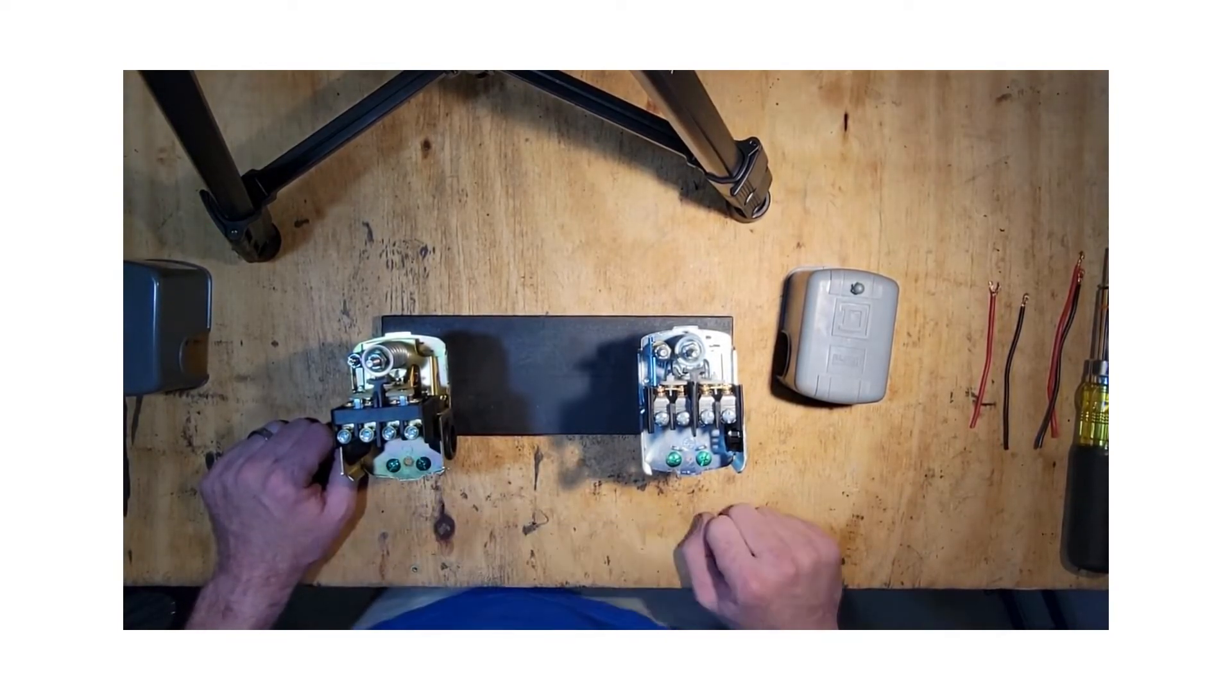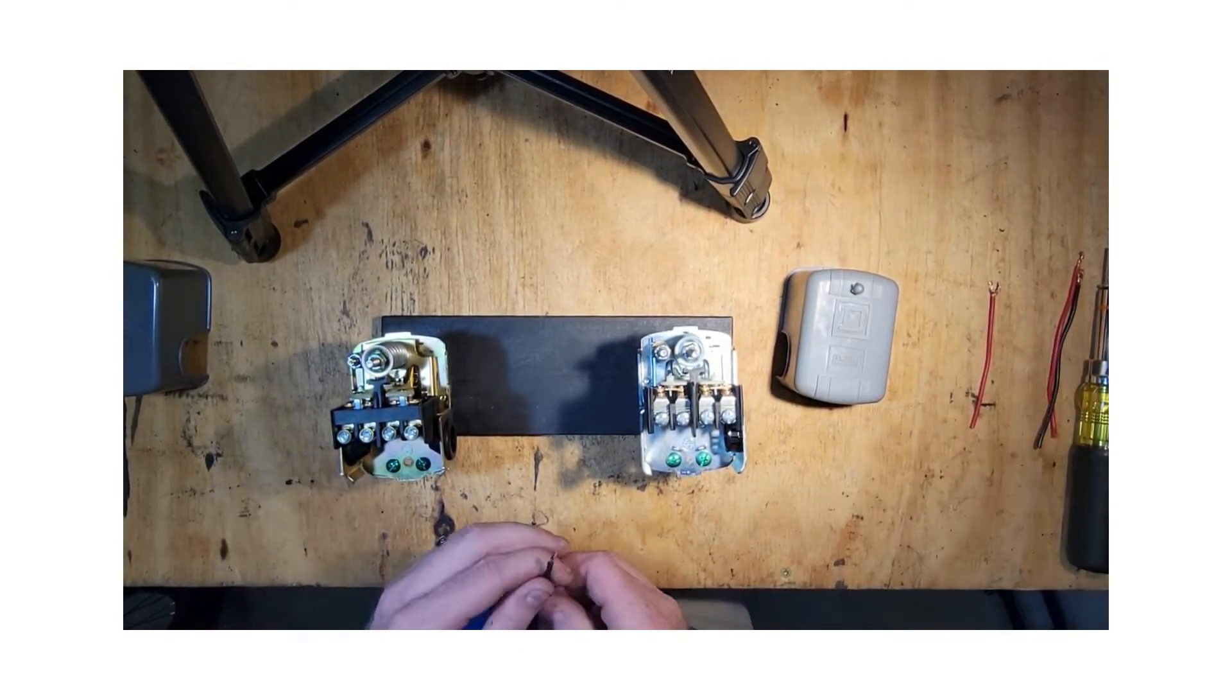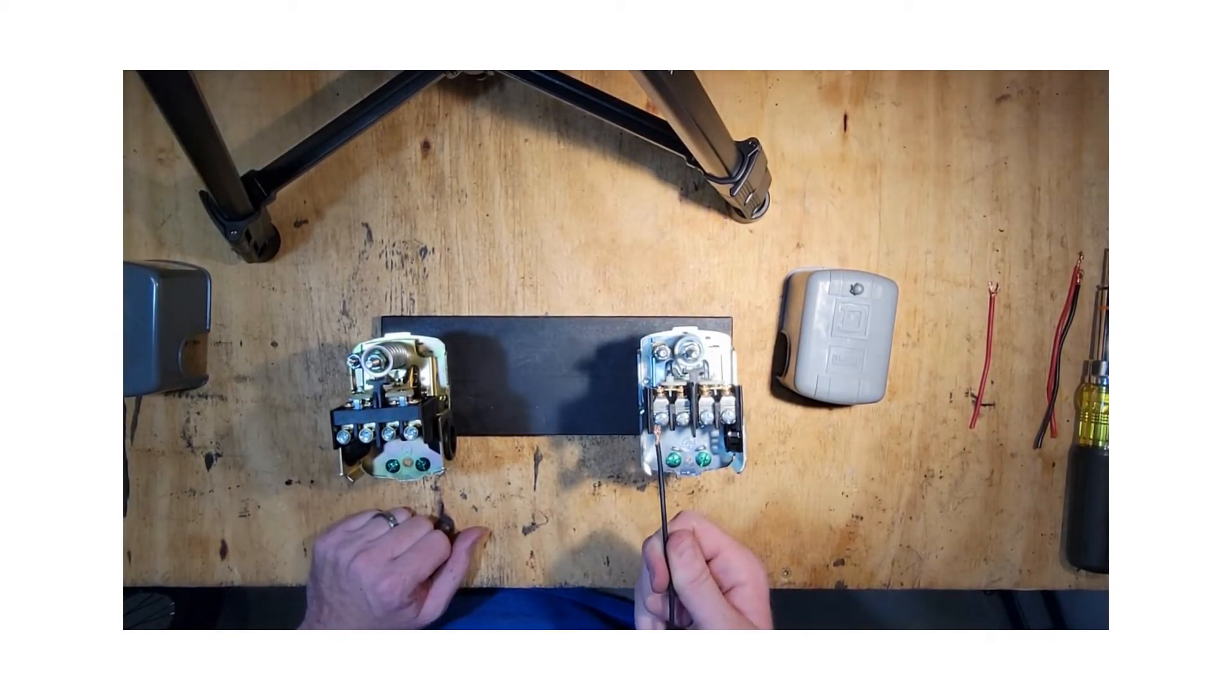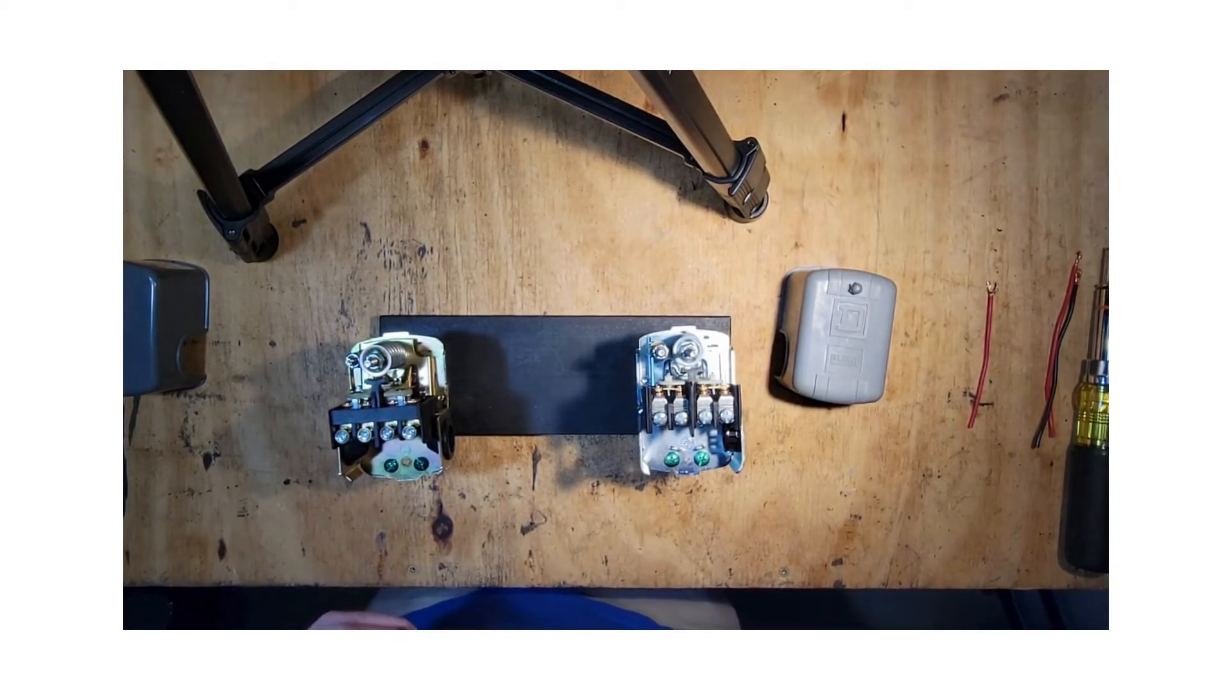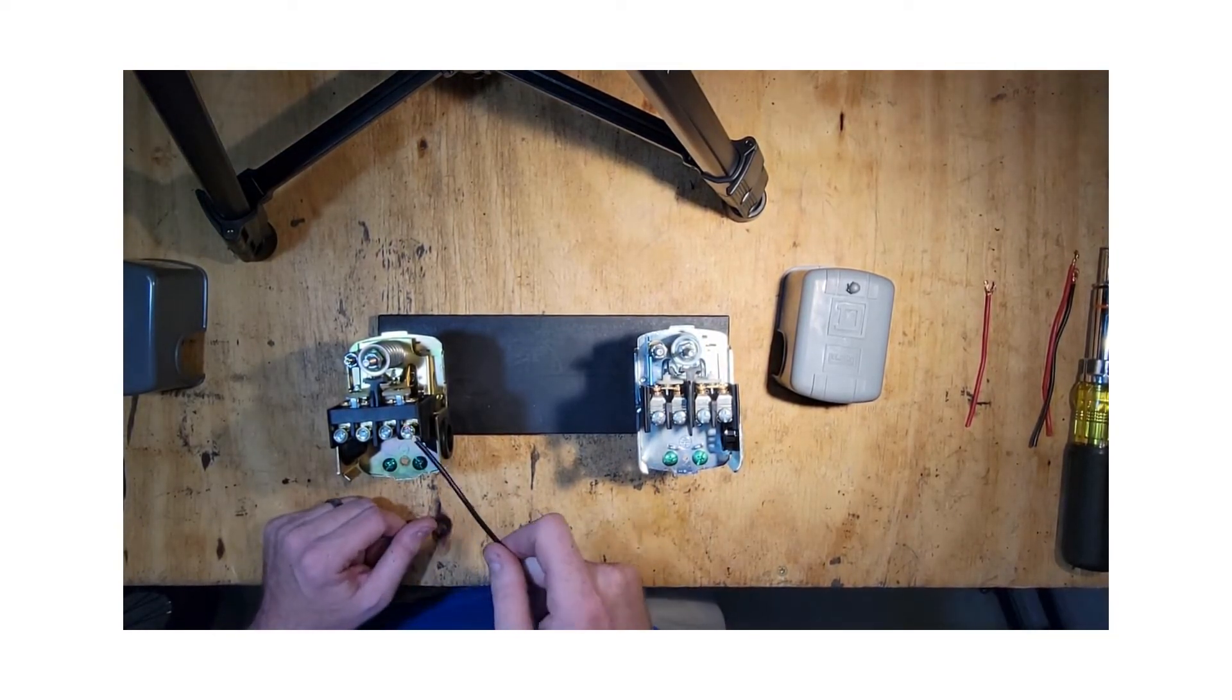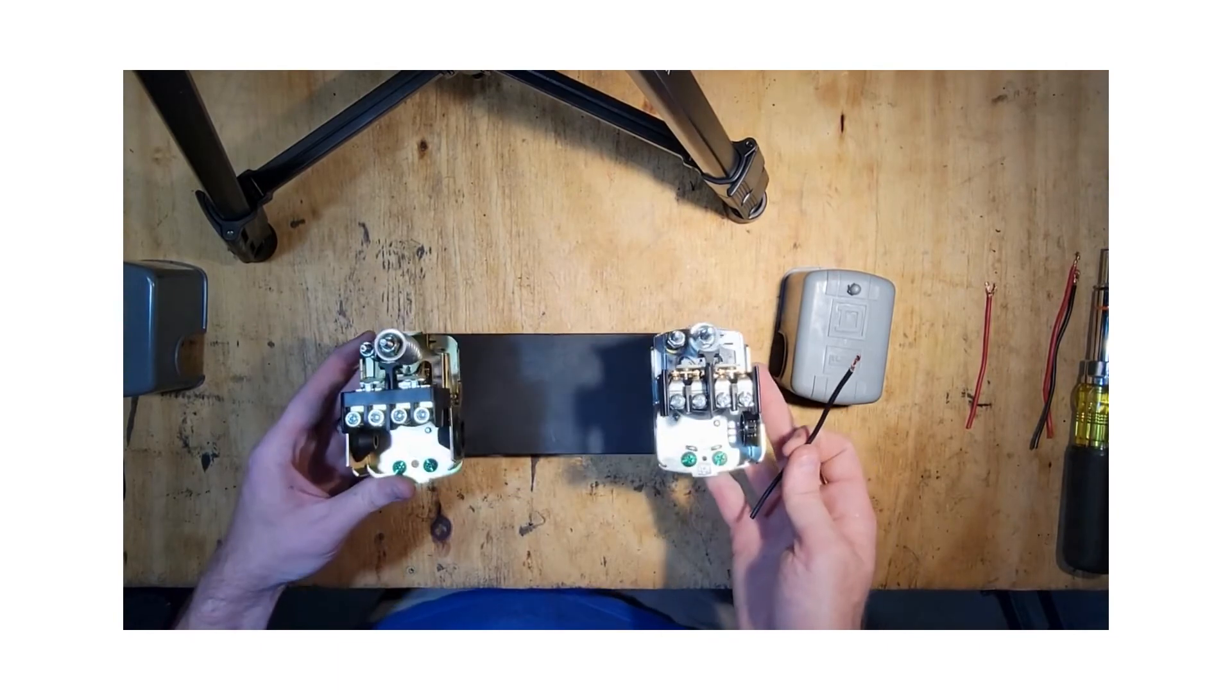Simply for the terminals. I really like these terminals. It saves me from having to carry around connectors to land my wires on because I don't like landing the bare wire on the Square D terminals. I just don't think it's—one, it doesn't look good, and two, to me it doesn't give a good secure connection.